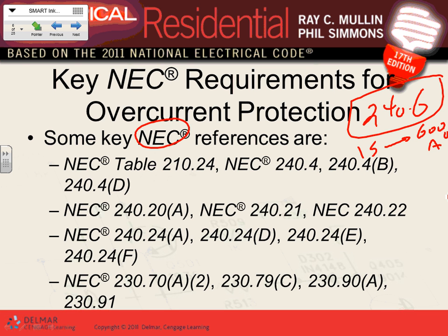Overcurrent protection devices shall be accessible. You have to put them in a place where people can have access to them. So these are all directly from the code that I'm looking at. You can't put them in a place where it can ignite the surroundings. It makes sense. The arc, if there's a short circuit, you put them in an area where there's gas. What do you think? Hazardous location, you blow up the place. So these are all from the code, guys. Shall not be located over steps or stairway. I can't put a panel over the steps or the stairway. The landing, no problem. The steps right here, you can't put a panel. That's all from the code.